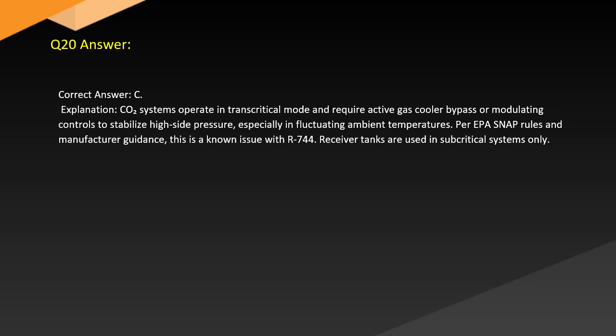Answer. Correct answer: C. Explanation. CO2 systems operate in transcritical mode and require active gas cooler bypass or modulating controls to stabilize high side pressure, especially in fluctuating ambient temperatures. Per EPA SNAP rules and manufacturer guidance, this is a known issue with R744. Receiver tanks are used in subcritical systems only.